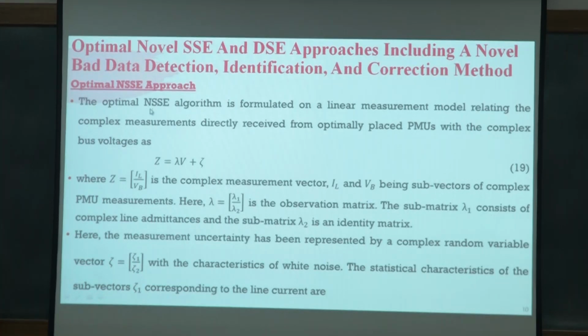This optimal, novel method together is called NSSE. The algorithm is formulated on a linear measurement model. Earlier, the measurement models we used were non-linear in nature. Now we have a linear measurement model relating the complex measurements directly obtained from optimally placed PMUs with the complex voltages. From a PMU, wherever it is located, we get the complex bus voltage and the complex line currents flowing through the lines connected to that bus.